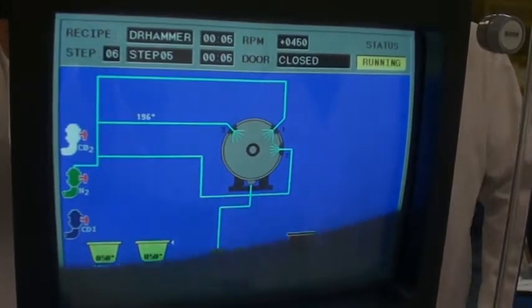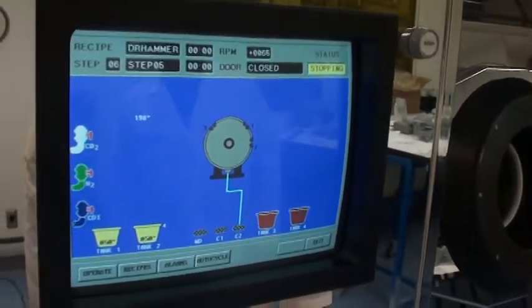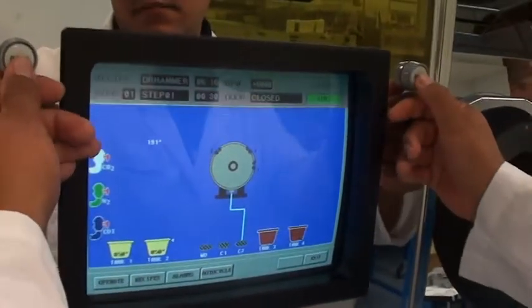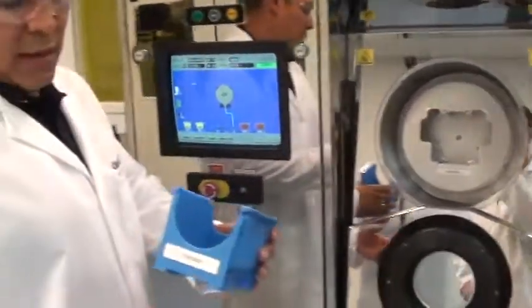You can see how it comes to an end on the recipe — it'll beep. The rotor will come to a complete stop. It's then when you can see 'Idle.' When you see Idle, that's when you can open your doors again. It says 'Open' — and you're good.